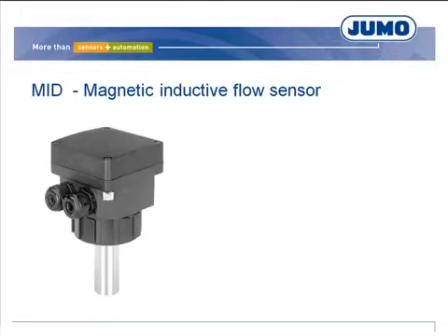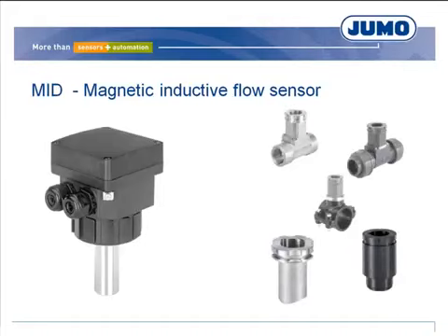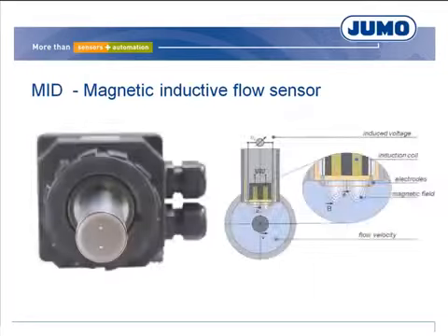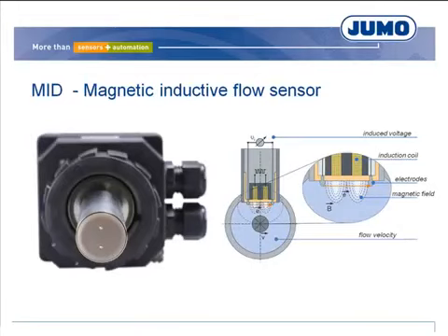This insertion sensor works according to the magnetic-inductive principle and represents a particularly compact type of the MID technology. It is combined with the same armatures as the paddle wheel sensor, but the measuring principle is completely different. The sensor works without mechanical components.